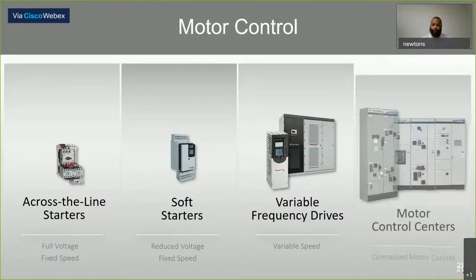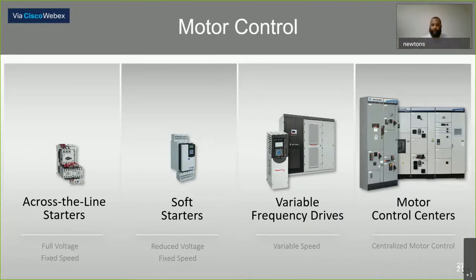And so big picture, these across the line starters, your soft starters, your variable frequency drives, and your motor control centers, where starters, soft starters, and VFDs, you can put these devices inside of MCCs. And again, we've been doing this for many decades. But with these being smart devices, that in essence makes our MCCs smart MCCs, and in our world we call them IntelliCenters. And the good thing about the IntelliCenters is that they are loaded with a smart managed switch, which will allow us to pull all the diagnostics and information that we said was available for us in our VFDs, soft starters, and our smart starters, particularly in the E300s.